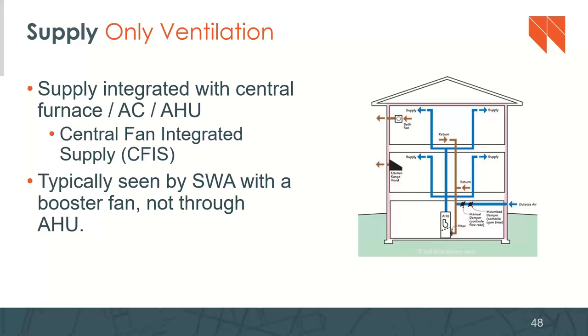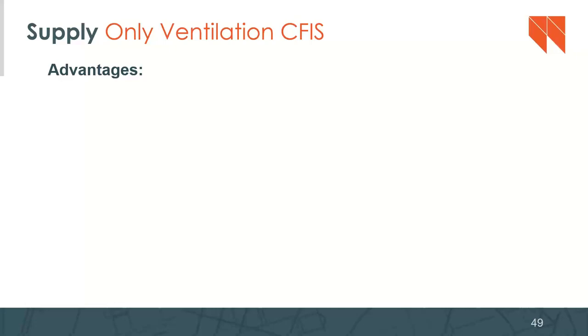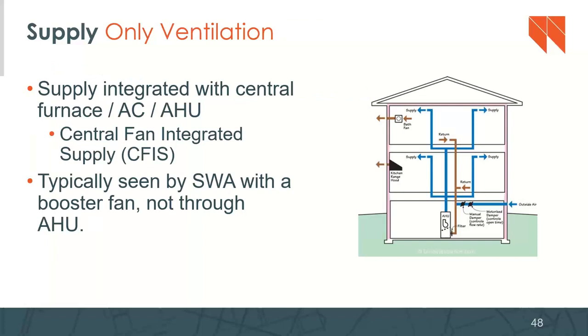So what we mean there is, well, I think our next slide is going to talk about this. Oh, it's just the advantages. All right, so I'm going to go back here because I have a diagram. What we see typically is that this outside air duct is going to go into the return side of the air handler. And so in a traditional central fan integrated supply, the thought was that when the air handler turns on and there's a negative pressure created in the return duct, it's also going to pull the outside air and bring it in. And what we're saying is that on this outside air duct, we usually need to see an inline fan, a booster fan, right?